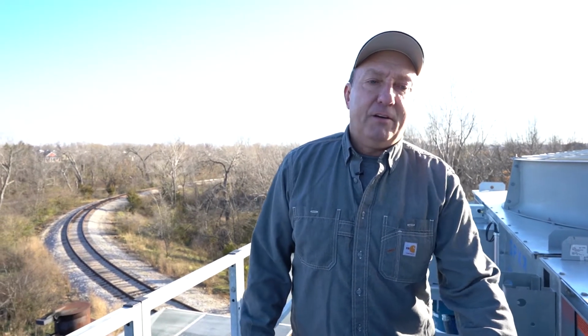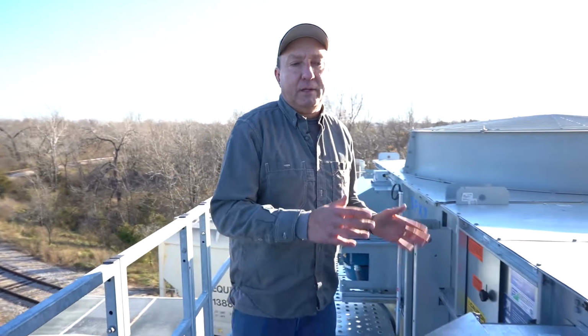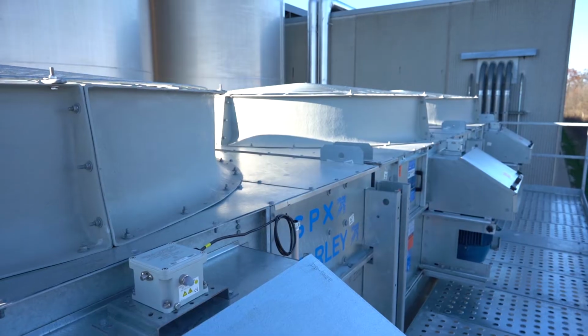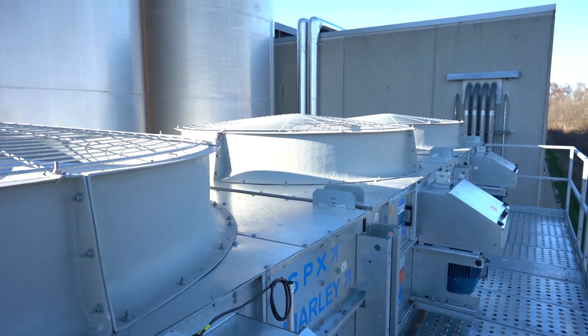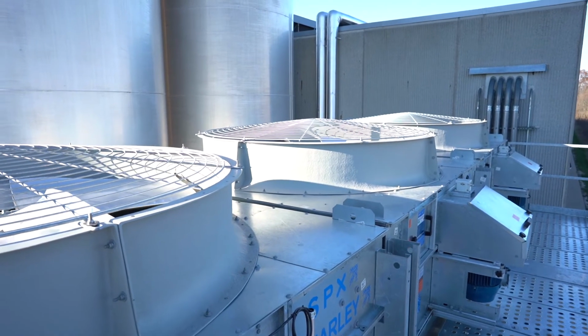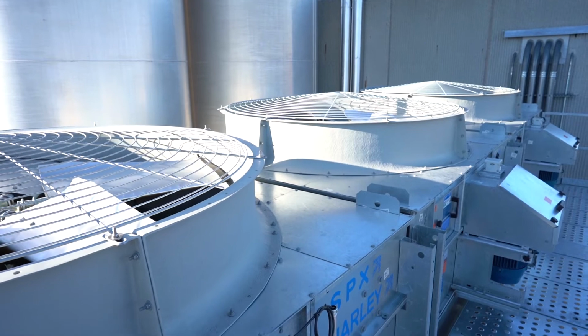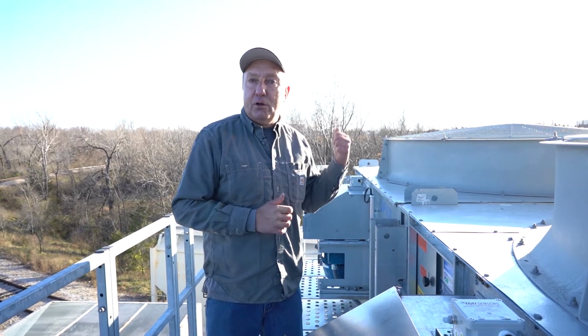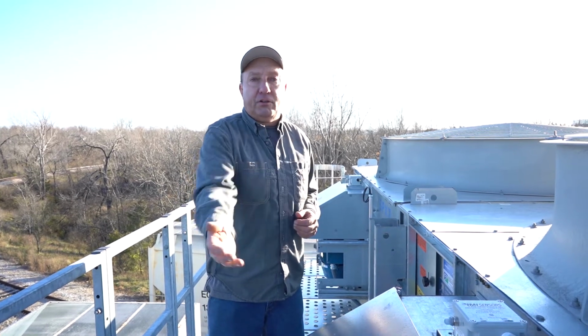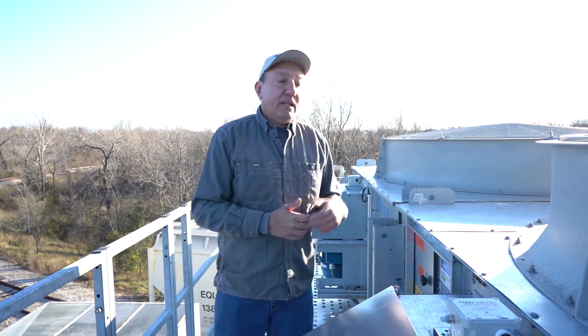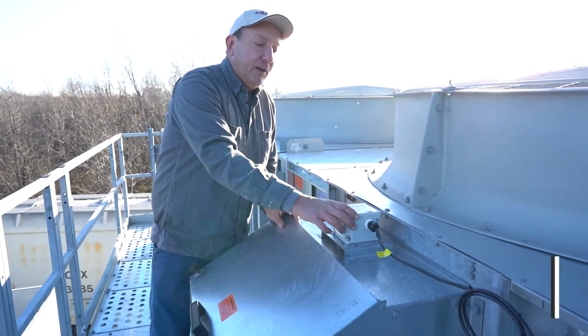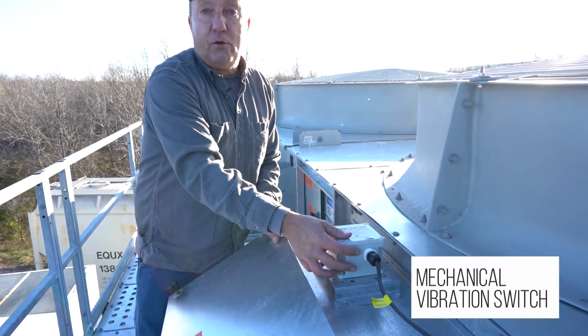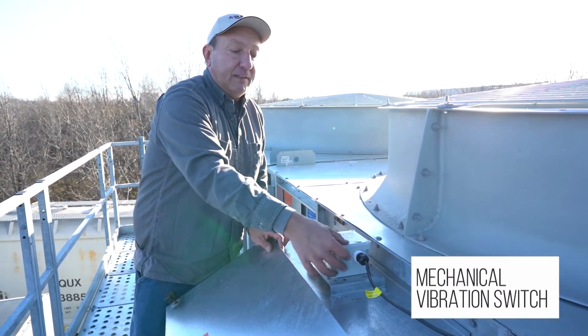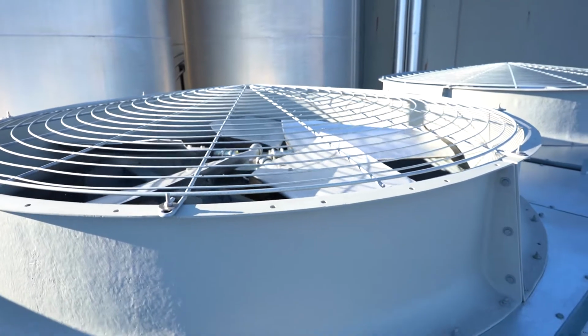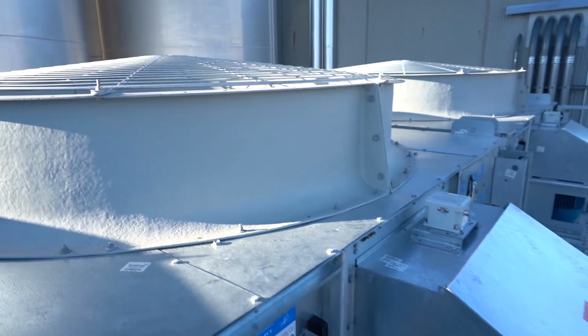Okay, now we are up on top of the Marley SPX MD model towers. Once again, we have 3 individual cooling towers, 1 for each chiller circuit, but in this case, the return water is in series. So when we're running one chiller, we actually circulate water through all 3 towers, and then they can stage up based on the VFD flow rates and depending on which circuits are energized or in operation at the time. Each circuit is protected by a mechanical vibration switch. We have this in series with the overload. So if the system was to get a fault at the HMI, we have a message telling you to inspect the mechanical vibration switch or the motor overload.